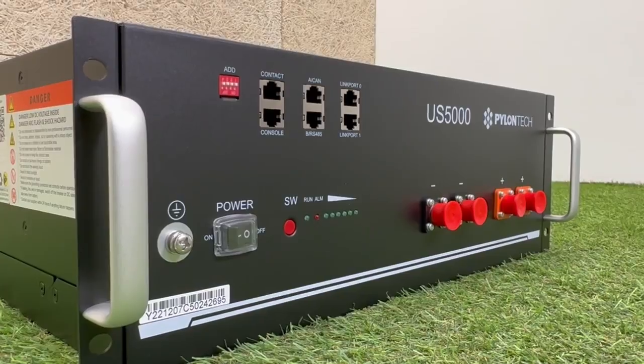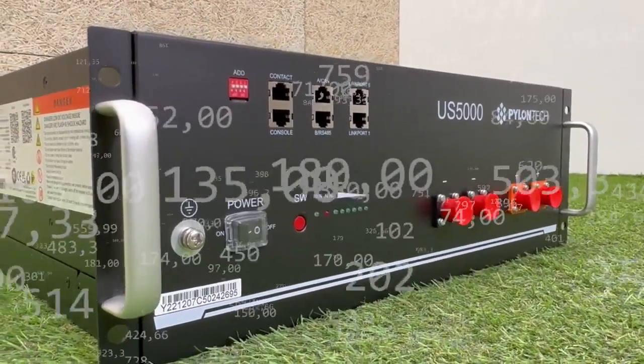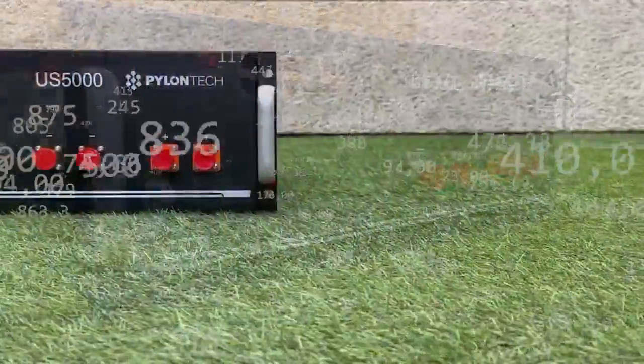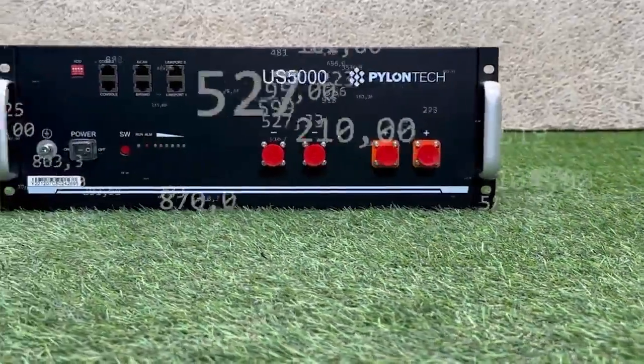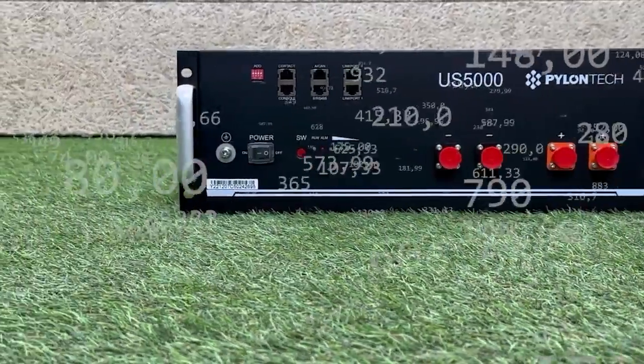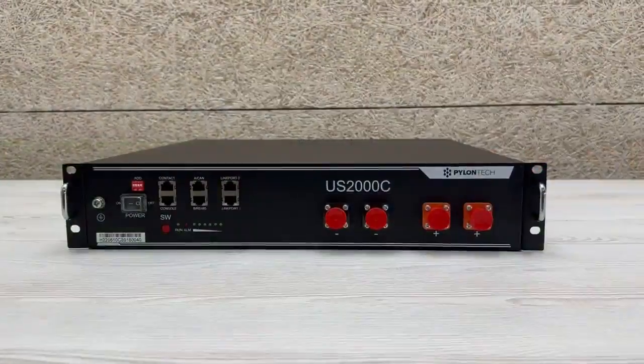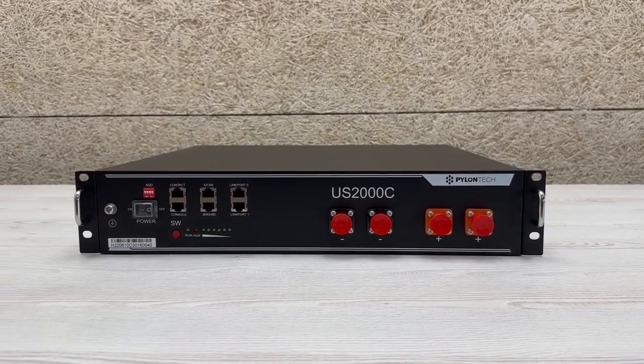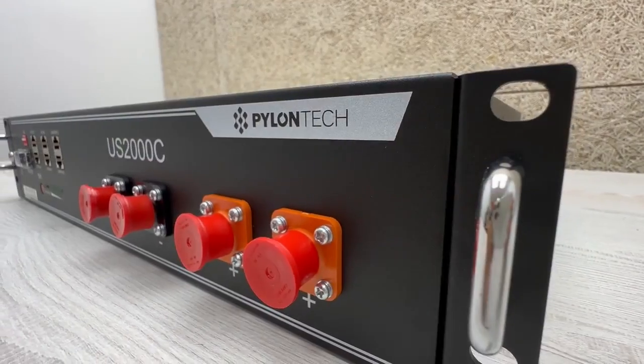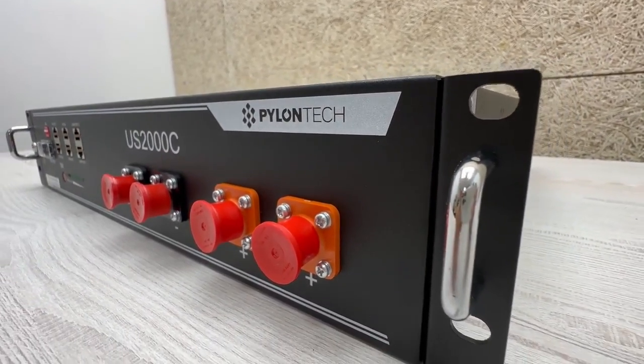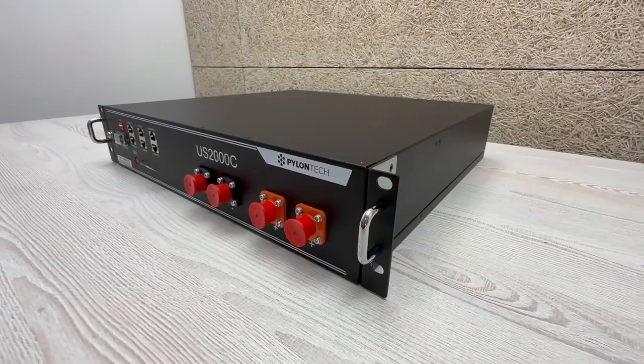In conclusion, with this software we can monitor in real time the status of our Pylon Tech battery, download the history of records or logs to be able to perform a check if we have had some kind of error or failure, and we could even perform a firmware update. The latter, the firmware update, can only be performed by the official Pylon Tech technical service, because if an external person performs it and there is an error, the battery would not be covered by the official warranty of the Pylon Tech brand.